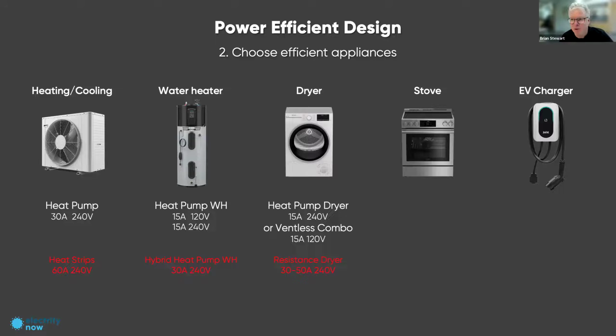Drying is another place where you can save a lot, because a typical electric resistance dryer requires 30, and in some cases as much as 50 amps for the circuit. But you can get a heat pump dryer that runs on 15 amps, and these ventless combo machines are fantastic. Now you've got one circuit for both washing and drying running on just 15 amps. So anytime you can combine loads into one circuit, it's another way to save space and amps on your panel.